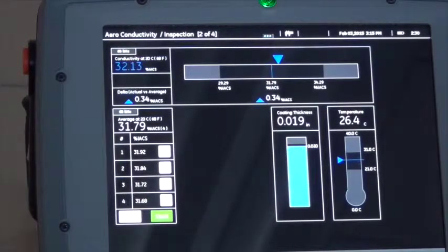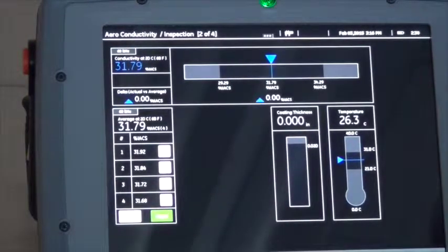So if we stack this up, go to 30 mils total of coating, you notice the conductivity reading starts to develop some error, and the coating thickness graphical measurement has alarmed to indicate that you've gone out of an acceptable range for measurement. So your measurements may still be useful, but just know that your accuracy may be impacted a little bit. So aside from coating, the other factor that has a major impact on accuracy is changing temperature.